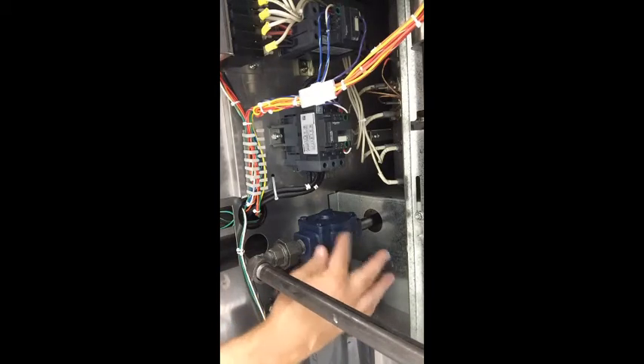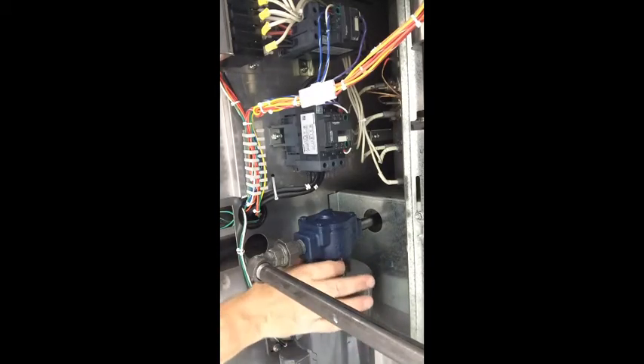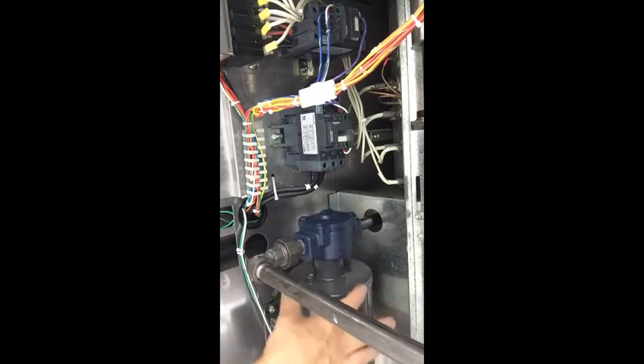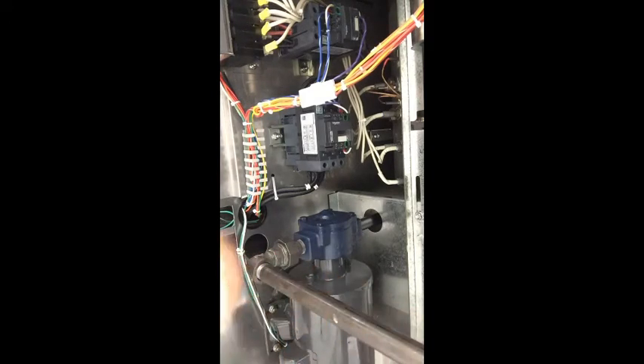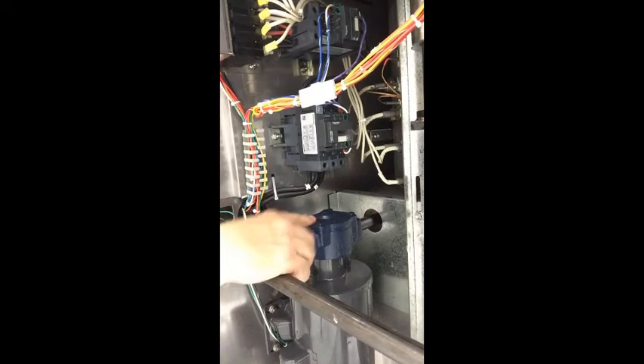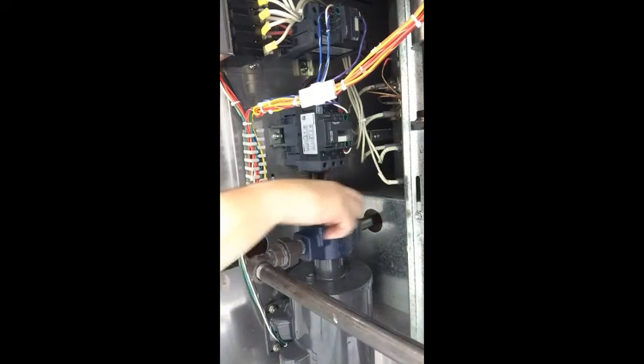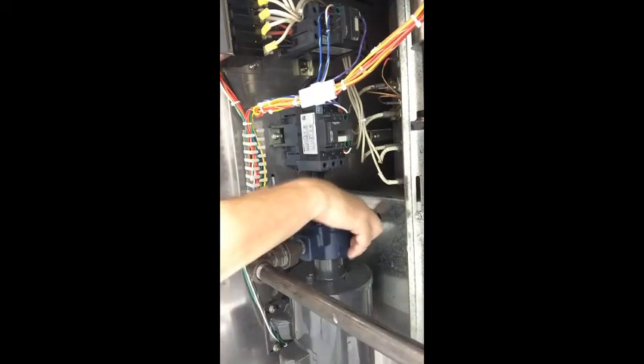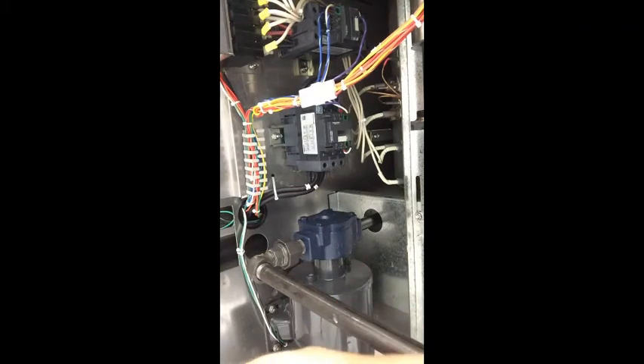To remove just the pump, you've got set screws right here. There's 3 set screws on this little snout on the motor. And you can separate those two once you get it out, just by undoing those set screws. So again, take it loose here. Make sure, again, oil is going this way. It's coming from the front, going to the diverter valve.